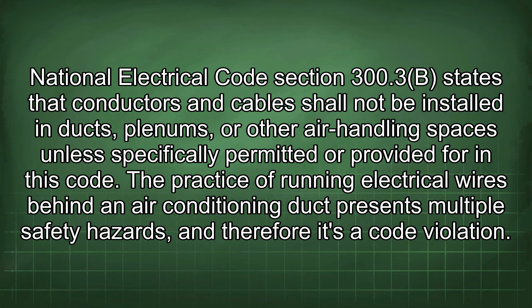National Electrical Code Section 300.3(B) states that conductors and cables shall not be installed in ducts, plenums, or other air handling spaces unless specifically permitted or provided for in this code. The practice of running electrical wires behind an air conditioning duct presents multiple safety hazards, and therefore it's a code violation. There are several key reasons for this prohibition.